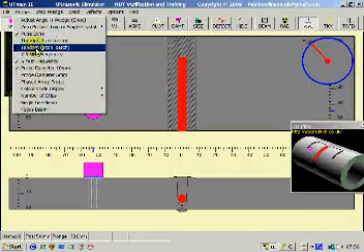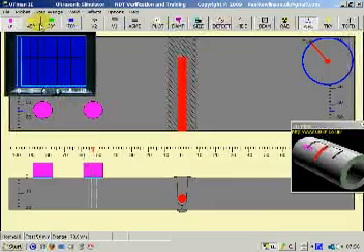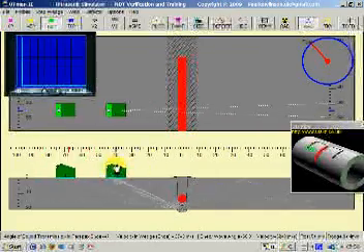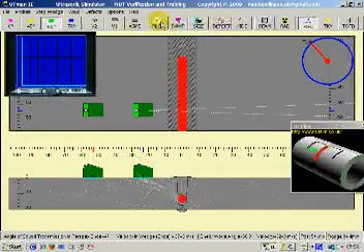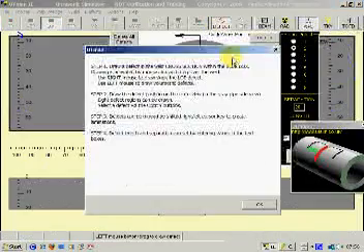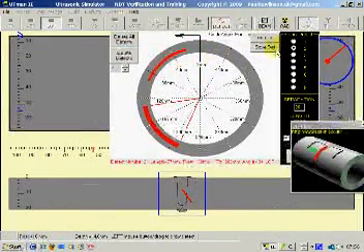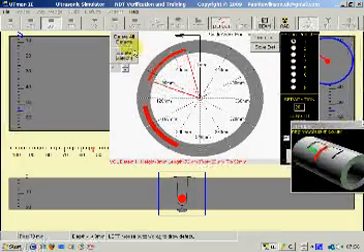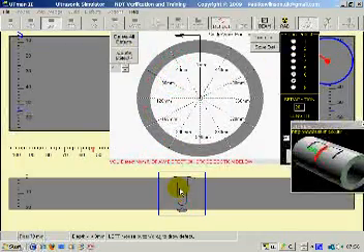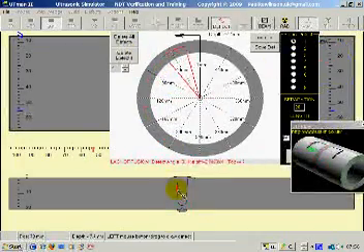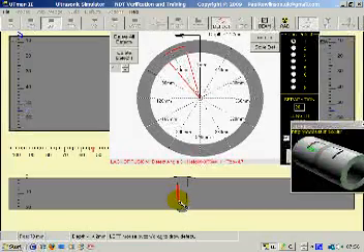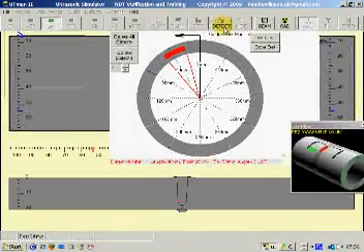Now also we've got other methods of testing. We've got pitch and catch, which essentially is two probes. I'll put a line in here with the right mouse key representing lack of fusion.